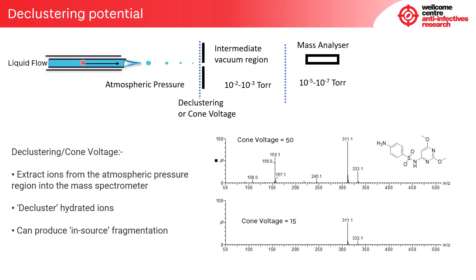One other parameter worth mentioning is the declustering potential, or cone voltage, which is applied to the front of the mass spectrometer. This is used to aid in the transfer of ions from the atmospheric pressure part of the source into the intermediate vacuum region. Different manufacturers have different names for this voltage, but the effect is effectively the same. It also helps to break up any clusters of hydrated ions trying to enter the mass spec. While it can increase the response of an analyte, it can also produce in-source fragmentation.